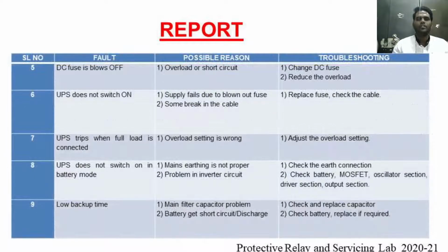After this, another fault may be that the DC fuse is blown. For this condition, it happens because of overload or short circuit. So for that one, I need to change the DC fuse and try to reduce the DC overload conditions.